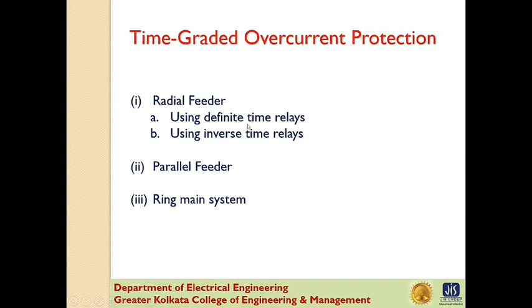We discussed time graded overcurrent protection for radial feeder, parallel feeder and ring main system. In radial feeder, there are two methods: using definite time relays and using inverse time relays. Now first start with radial feeder using definite time relays. The main characteristic of a radial system is that the power can flow only in one direction, from generator or supply end to the load. It has the disadvantage that continuity of supply cannot be maintained at receiving end in the event of fault. Time graded protection of a radial feeder can be achieved by definite time relay and inverse time relay.